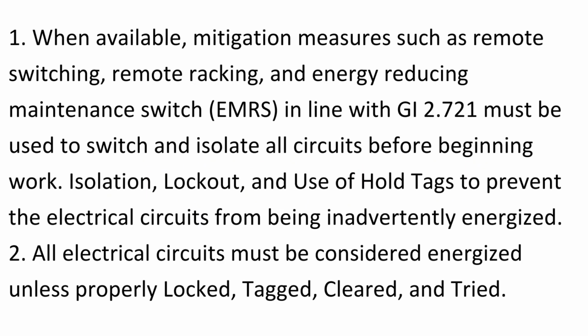Work practices. 1. When available, mitigation measures such as remote switching, remote racking, and energy-reducing maintenance switch, EMRS, in line with GI 2.721 must be used to switch and isolate all circuits before beginning work. Isolation, lockout, and use of hold tags to prevent the electrical circuits from being inadvertently energized. 2. All electrical circuits must be considered energized unless properly locked, tagged, cleared, and tried.